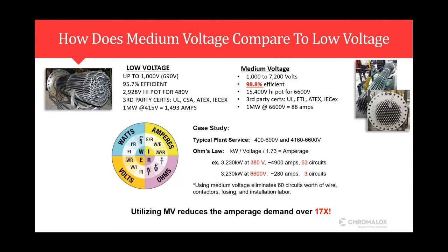So again, looking at the two technologies, not going to read it word for word, but you can see the major takeaways here. On the low voltage side, it's 95.7% efficiency compared to a medium voltage heater, which is nearly 99% efficient. So obviously from the operational side, there's a lot to take away from those increased efficiencies that the medium voltage gets you. But the other takeaway too, if you look at the 1 megawatt at 415 example there, that system would pull almost 1,500 amps. An equivalent system at 6.6 kV pulls only 88 amps. So you can see just the drastic reduction that medium voltage technology allows for you.